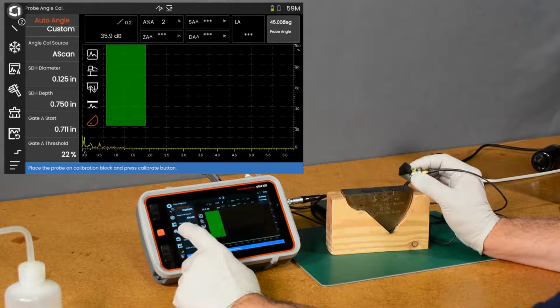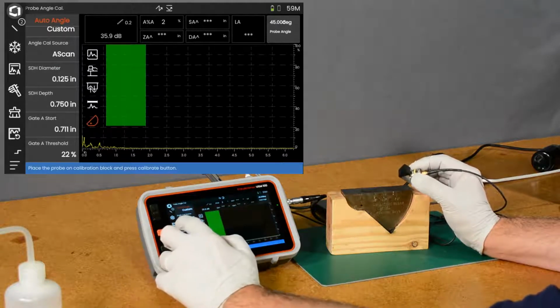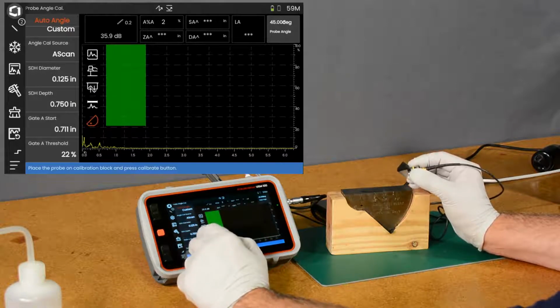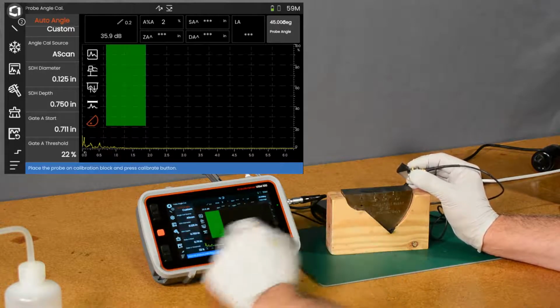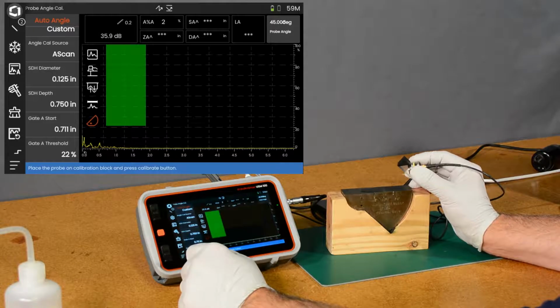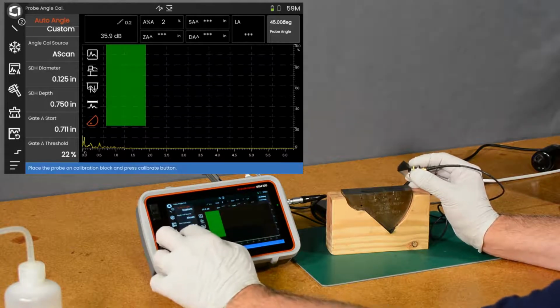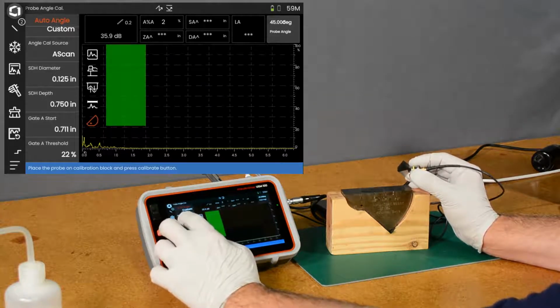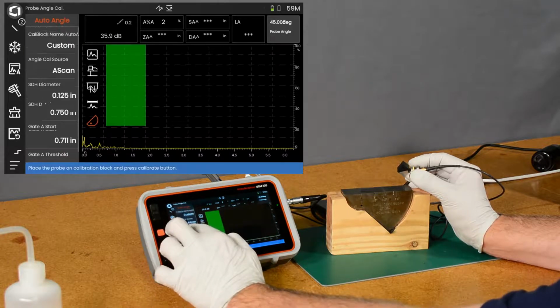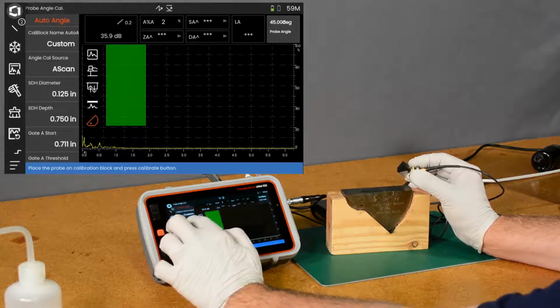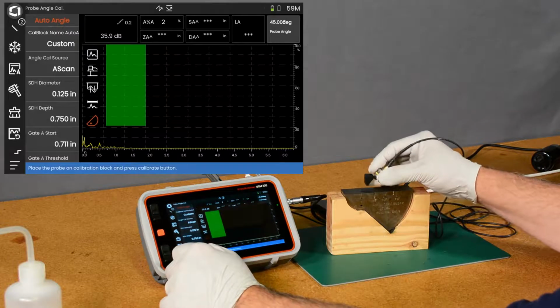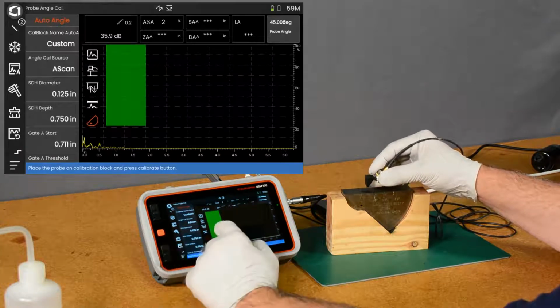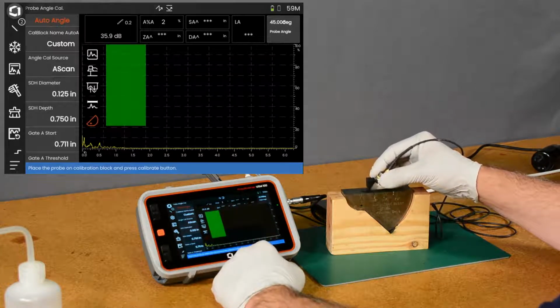You can see a couple of key parameters here. One is the side drilled hole diameter. I have already set that to 1/8 of an inch to match the block and 3/4 of an inch deep. Our gate starting at 0.7 inches. And we're going to use the A scan as the source for our peak measurement in the gate. So we're going to do that first.